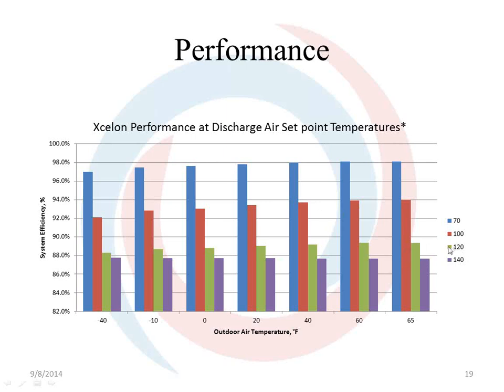So if you're using it for space heating too, you're still a lot higher than this typical power vented unit. And that's over the whole range. Remember, as you go up in outdoor air temperature, the efficiency could go down. And as you put different units together above 400, the efficiency drops and drops and drops. But this is at 88, 89 to 98% over the entire operating range.